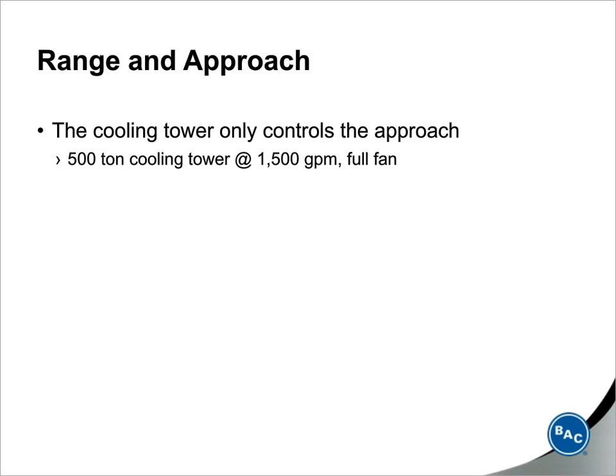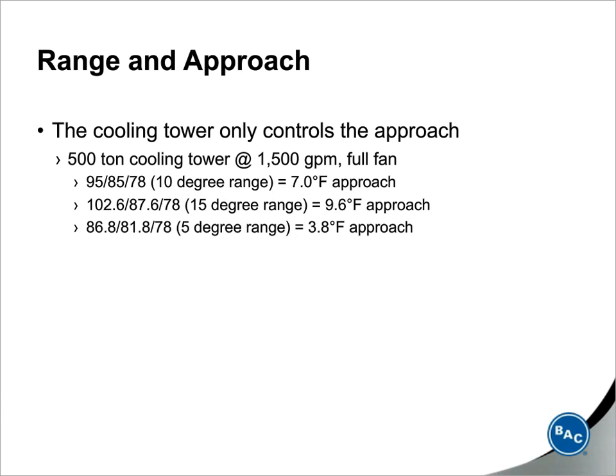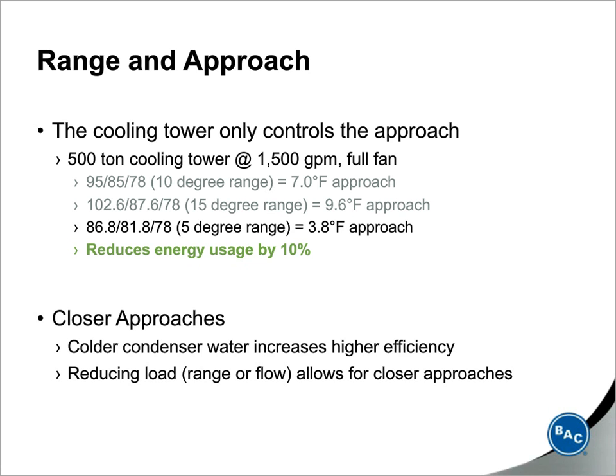Okay? So let's consider a 500-ton system design, assuming 1,500 GPM, which is 3 GPM per ton, through the condenser water loop. The range, which again is the difference between the water entering and leaving the tower, is determined by the size of the heat load removed from the building. So for each of the 3 conditions listed on the screen, a 500 nominal ton cooling tower can do this required duty at these design conditions. However, the last condition, which I highlighted here, shows it really offers the greatest system energy savings since it has a closer approach, which again is the difference between the cold water temperature leaving the tower and the ambient wet bulb temperature. A closer approach is going to reduce the amount of chiller work that's required.